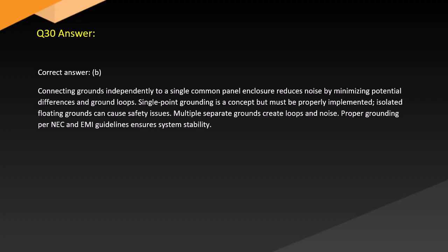Answer. Correct answer: B. Connecting grounds independently to a single common panel enclosure reduces noise by minimizing potential differences and ground loops. Single-point grounding is a concept but must be properly implemented. Isolated floating grounds can cause safety issues. Multiple separate grounds create loops and noise. Proper grounding per NEC and manufacturer guidelines ensures system stability.